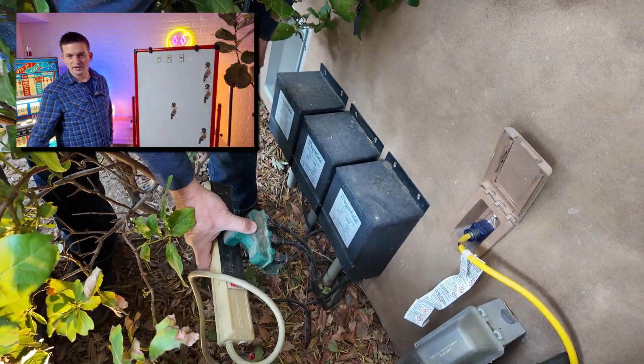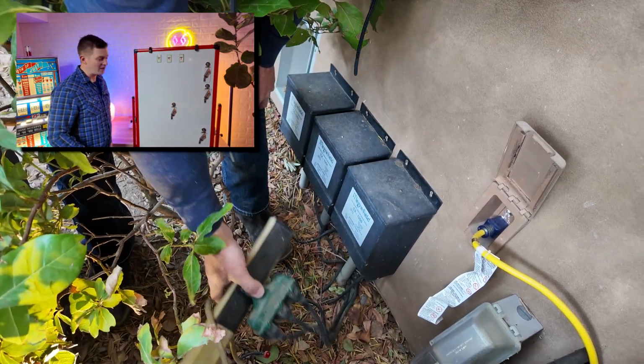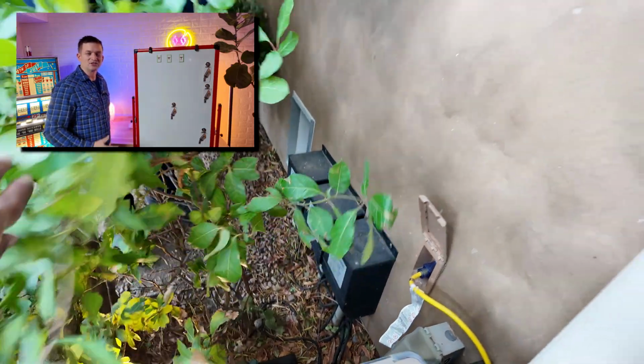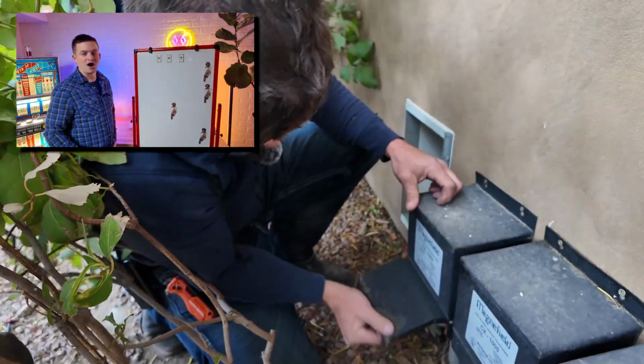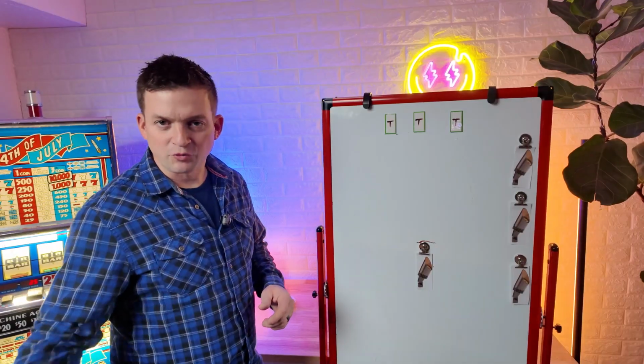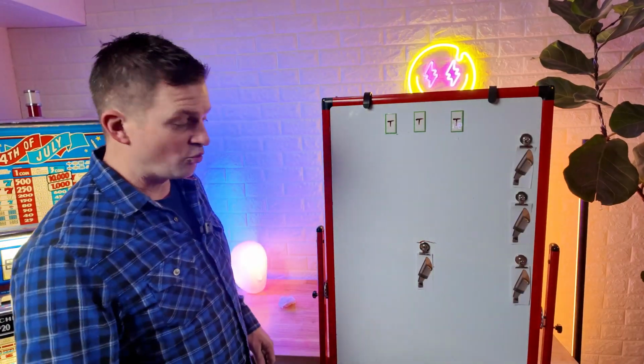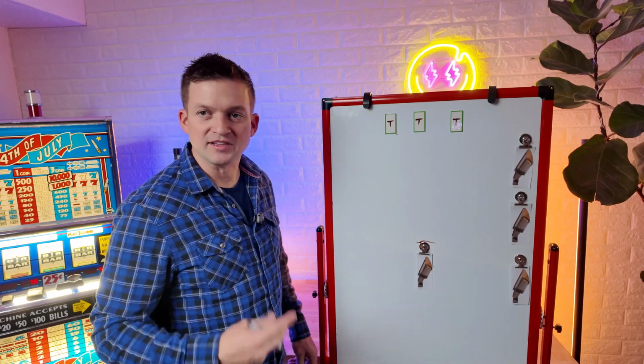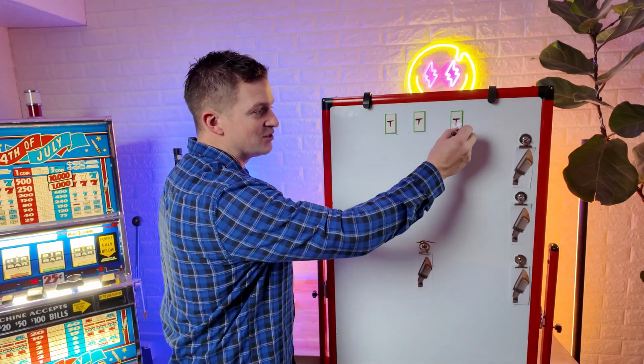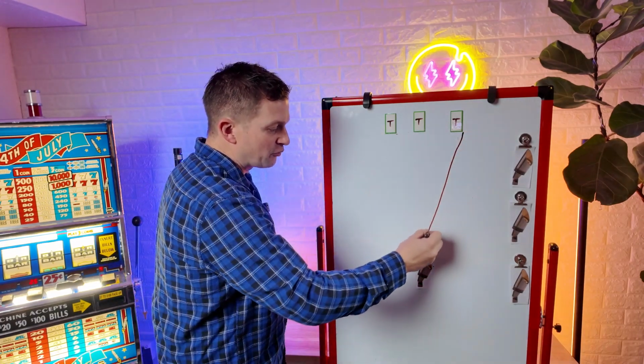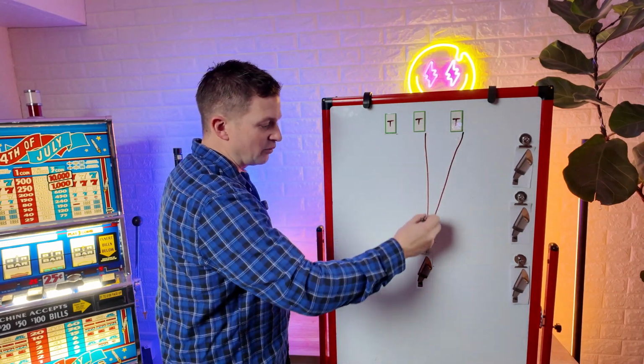question here. But as I dig a little deeper into it, what I realize is that I can turn off any single one of these transformers and this light remains on. It's only when I turn off all 3 transformers at the same time does this light go off. What we can derive from this situation is that we've got a single fixture in question that in some way, shape, or form has wiring from each of 3 transformers that interact with it.